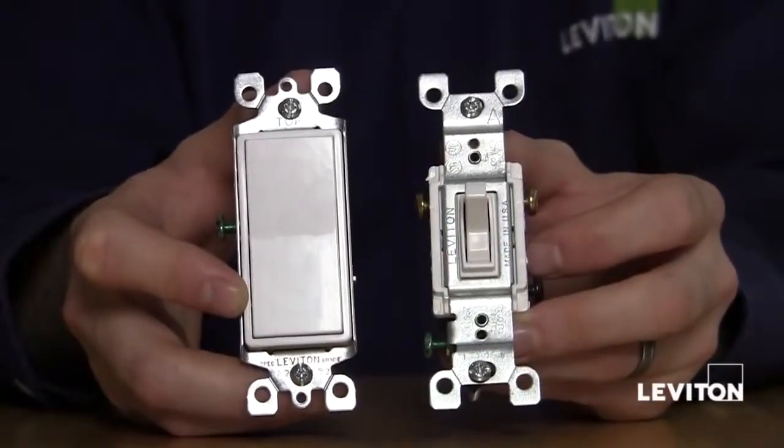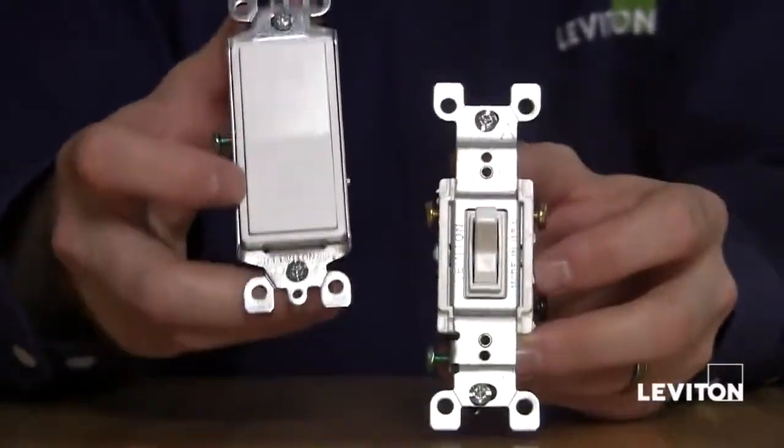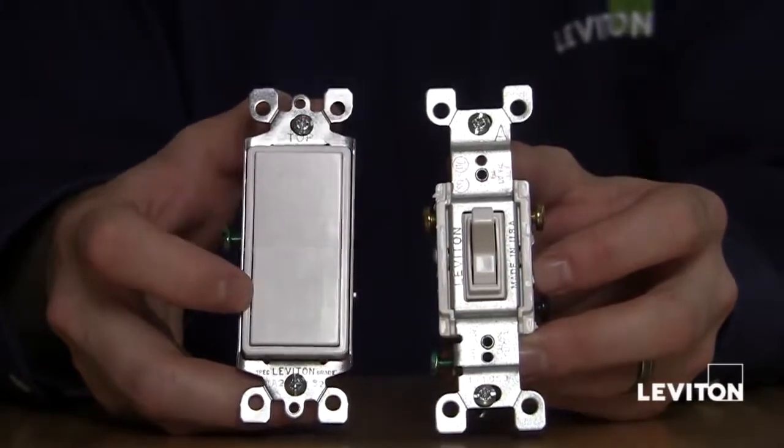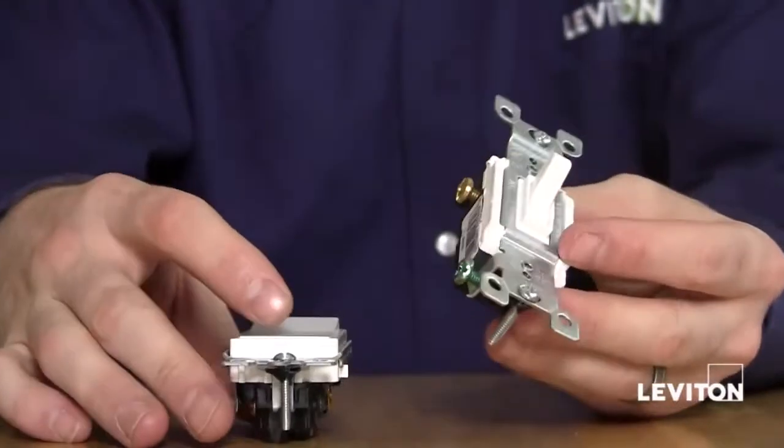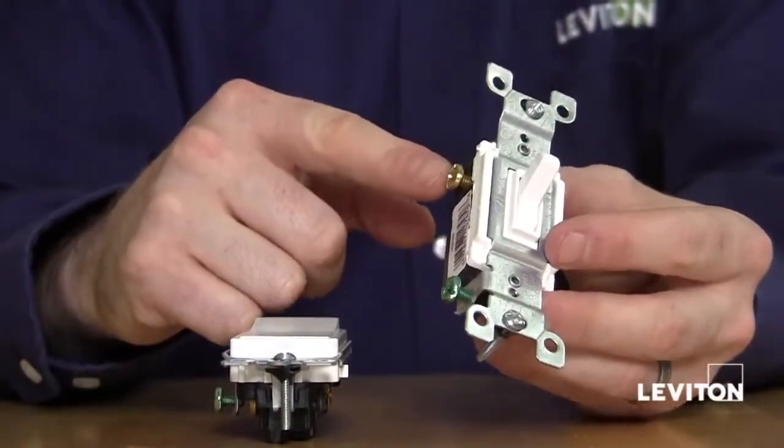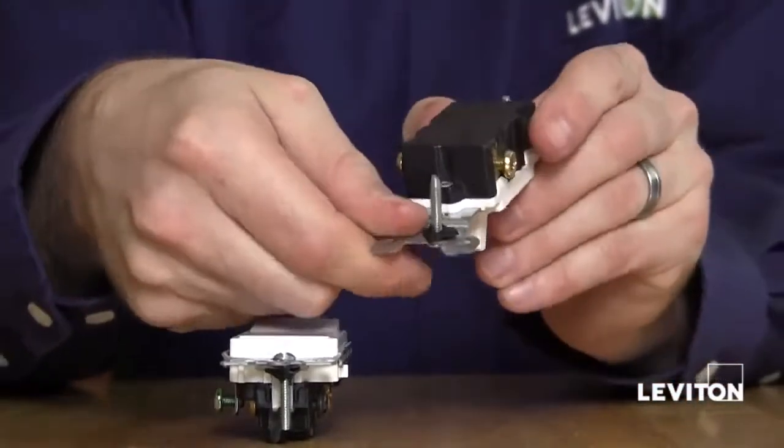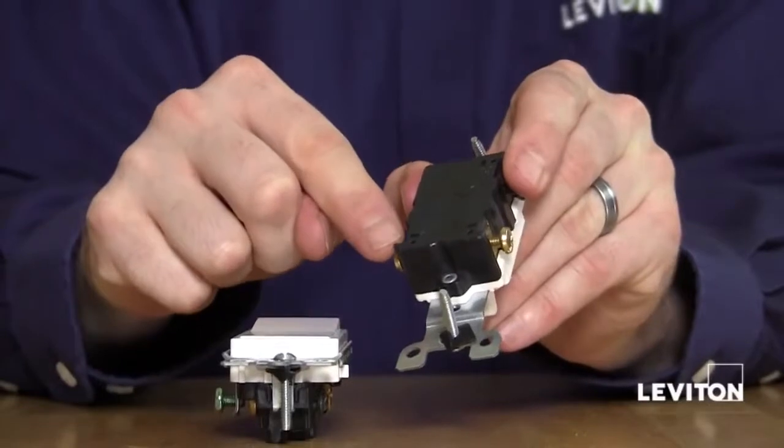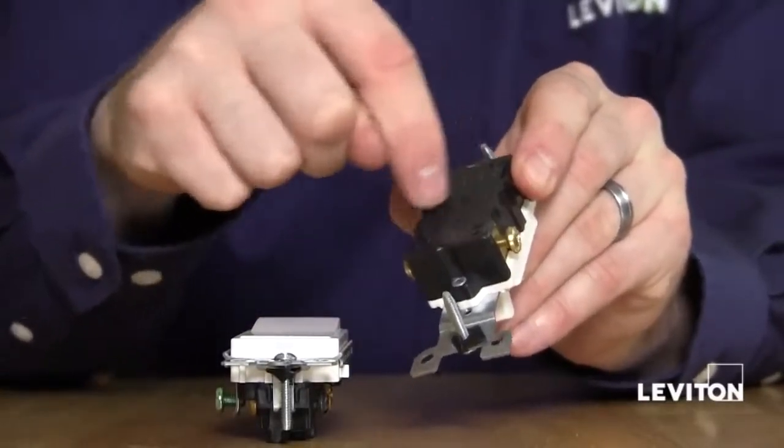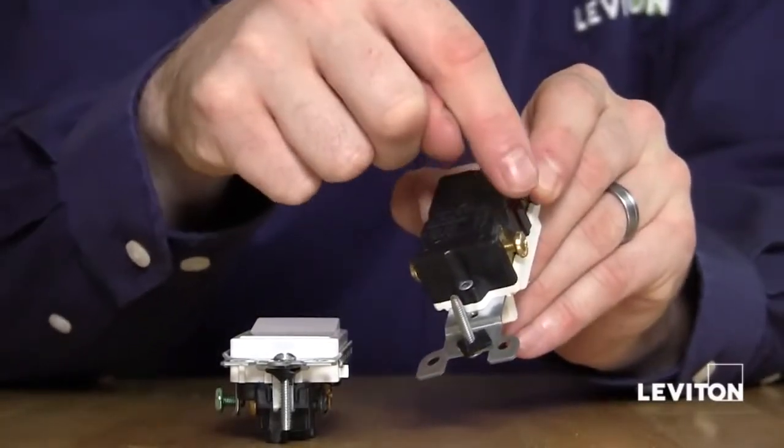So here's how it works. Remember the two traveler wires that go between either switch? One of these wires is always hot. By changing the state of the switch, you actually move power from one wire to the next, internally moving it from one brass terminal to the next.